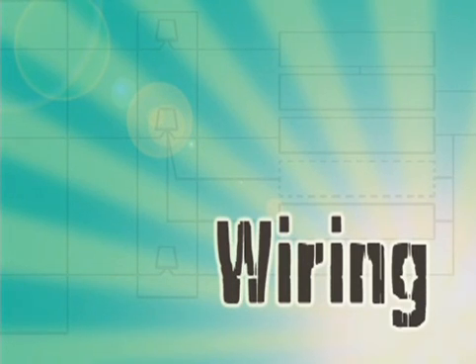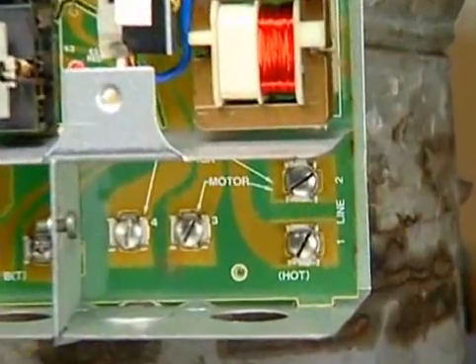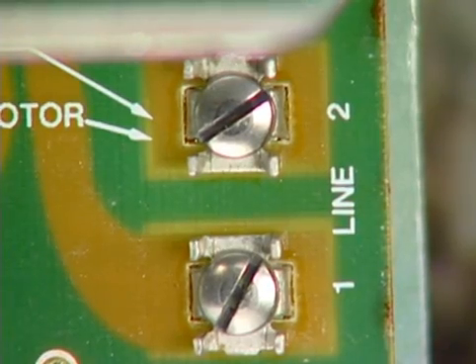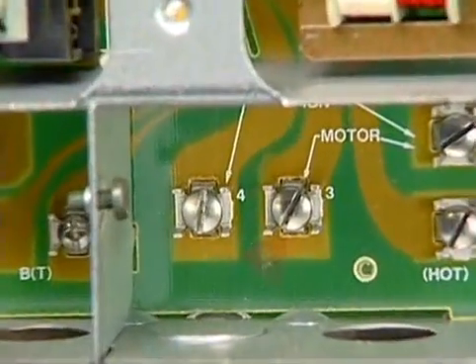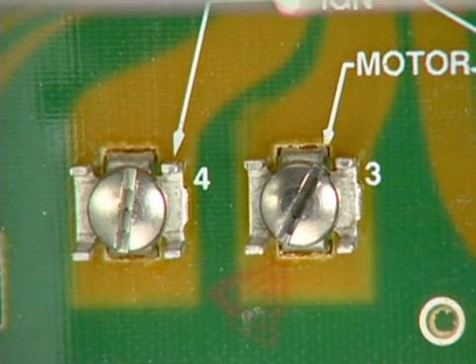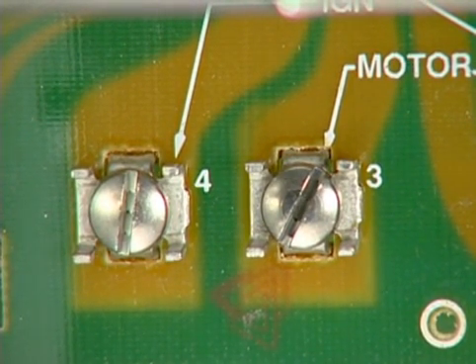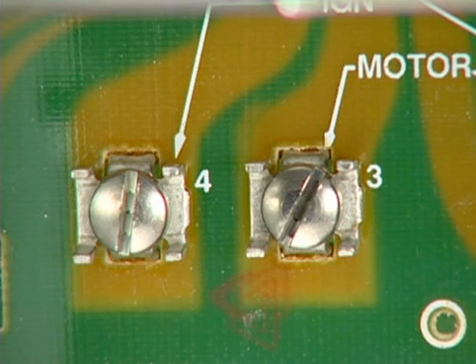Wiring of oil heat systems must always comply with all applicable codes and regulations, be completed in accordance with manufacturer's instructions, and be performed by a qualified technician. The power or hot lead from the limit control is connected to terminal 1. All neutrals are connected to terminal 2. One wire from the burner motor and one from the oil valve, if used, are connected to terminal 3. And if the unit operates on interrupted duty ignition, one wire from the transformer is connected to terminal 4.